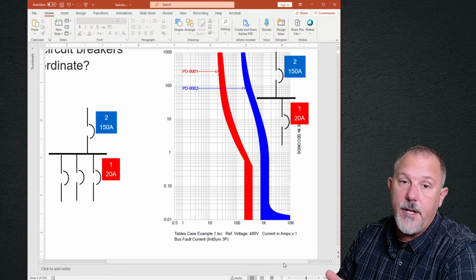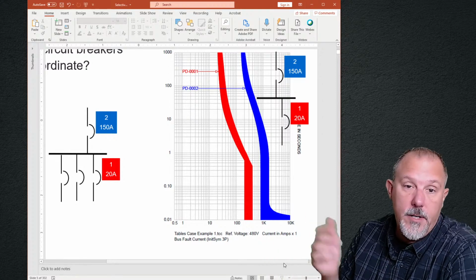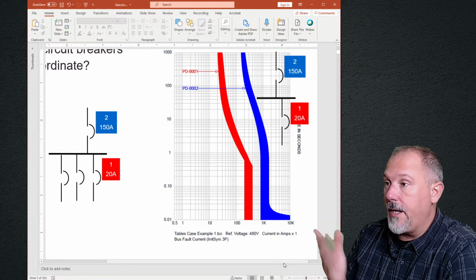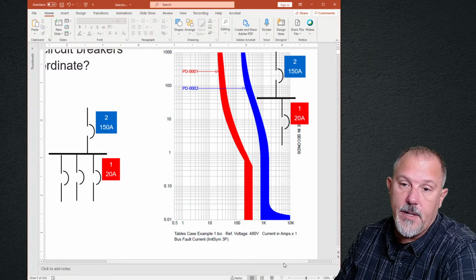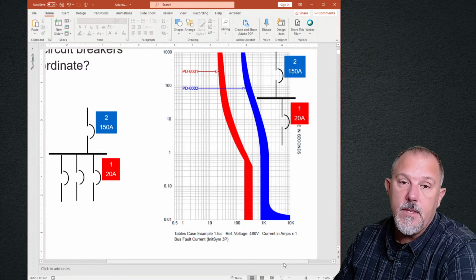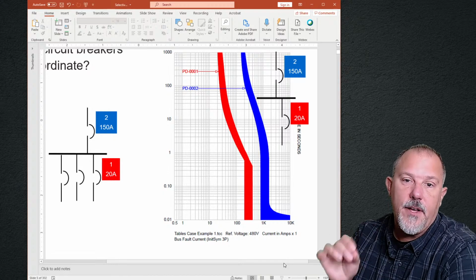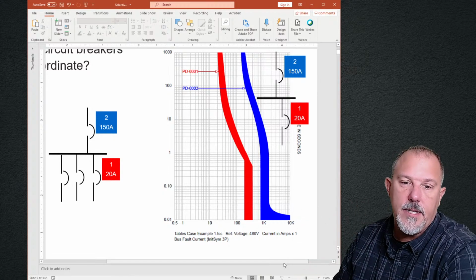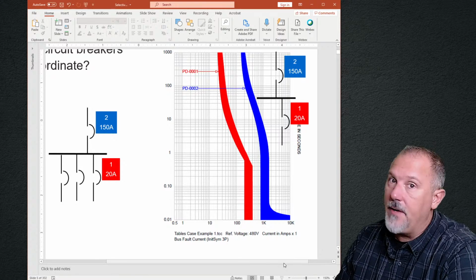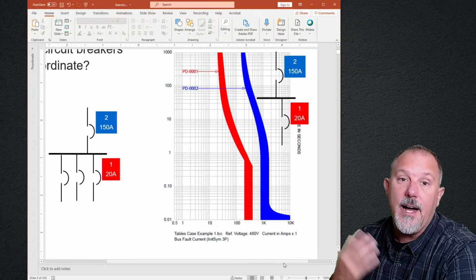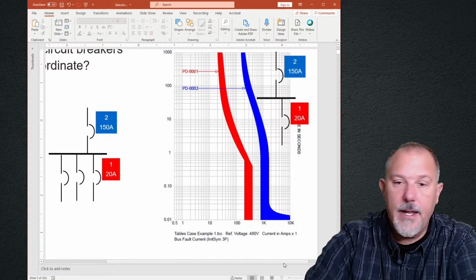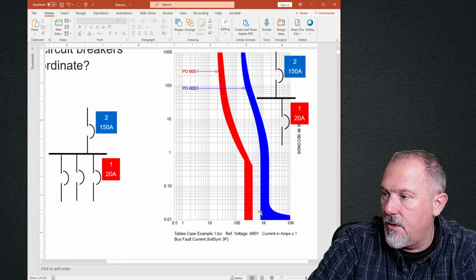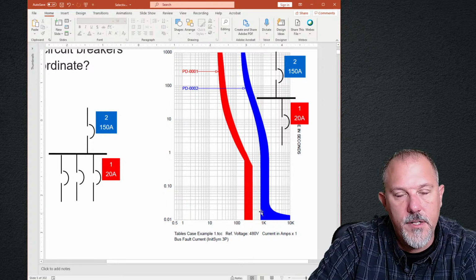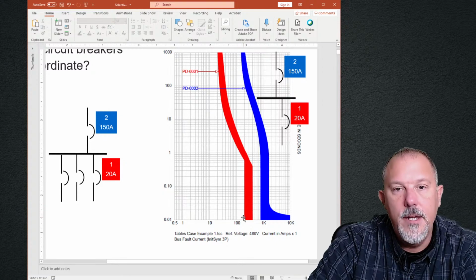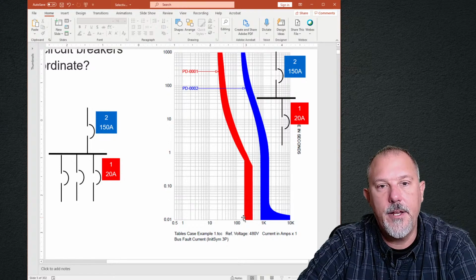In the case of coordination, I don't need to evaluate it. So they coordinate. Yeah, they coordinate. They look great from a coordination perspective, but they do not. I haven't done any evaluation. If I just looked at these curves and said they coordinate down to 0.1 seconds, I haven't done any evaluation of fault current. All I know is I have separation of curves down to 0.1 seconds. And that value on this curve, right before that leading edge of this blue curve, which is the overload region of that circuit, then I know that the downstream device will open and not the upstream device.